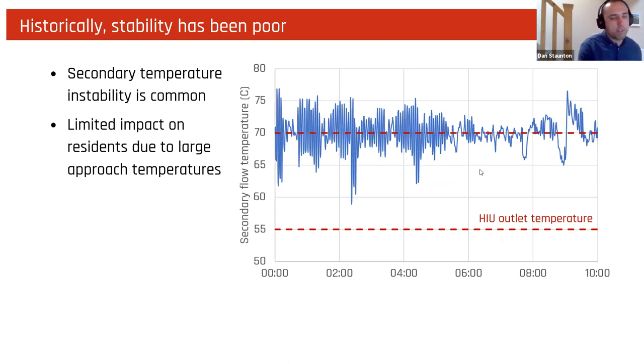Historically, though, outlet temperature stability from plate heat exchangers has been poor. So the data on the right-hand side here shows the secondary flow temperature off a plate heat exchanger, taken just a couple of weeks ago from the site. During periods of low demand, so before around 5 o'clock in the morning, we're getting really quite unstable temperatures. The target outlet is 70 degrees, but it's varying between 75 and 60 degrees.